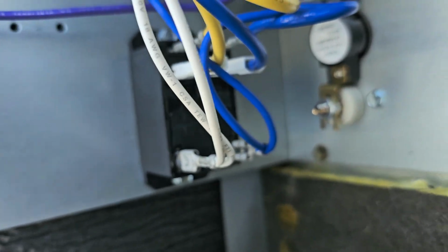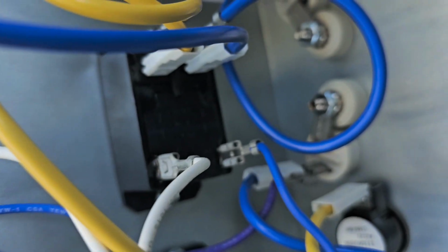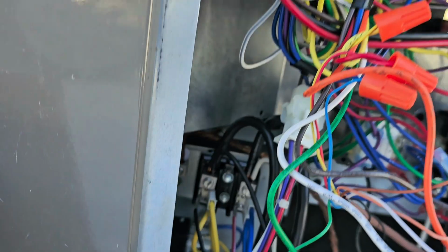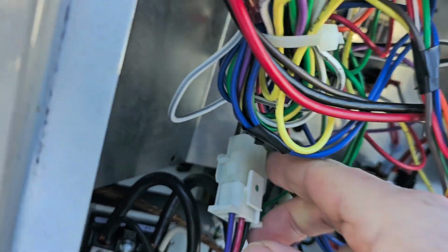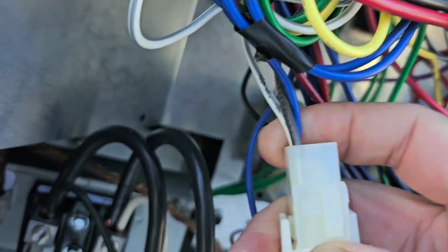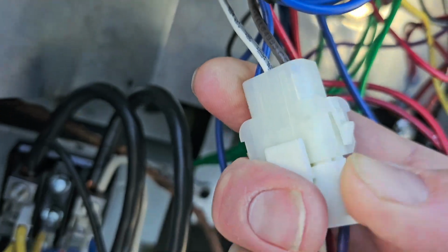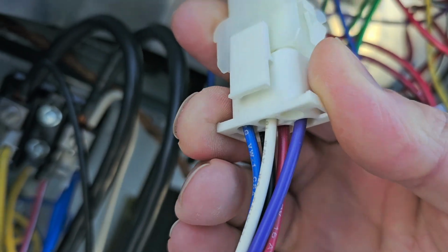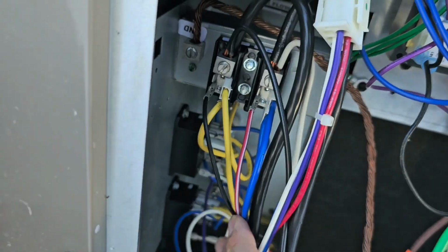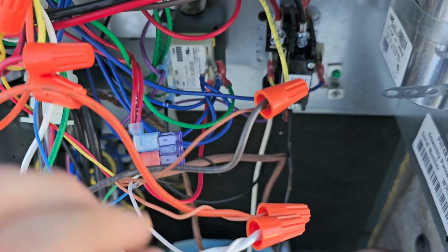Okay, and I don't see a brown wire. I see a white wire energizing that relay, and I see another white wire energizing that relay. And I bet you, if I look at this plug right here, you see the white wire that goes in and the brown wire? The white wire comes out, but the brown wire doesn't. So the brown wire is not being used. So what do I need to do?